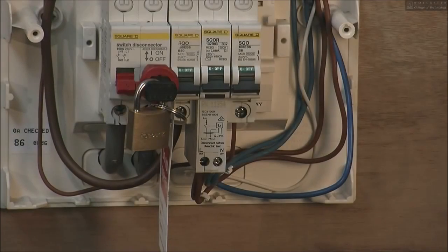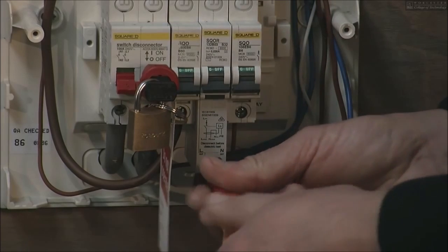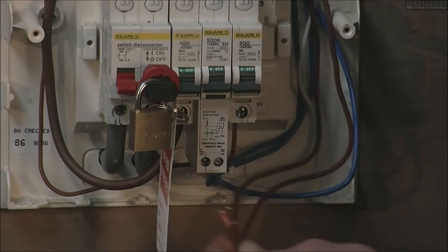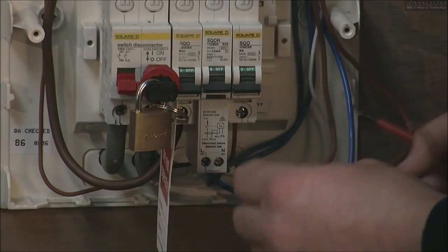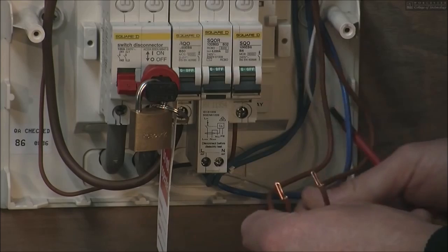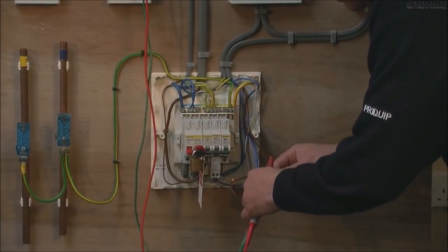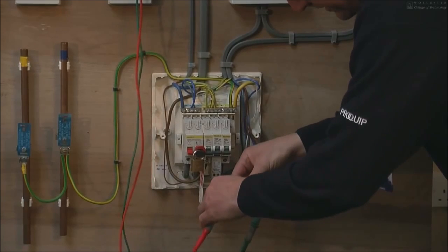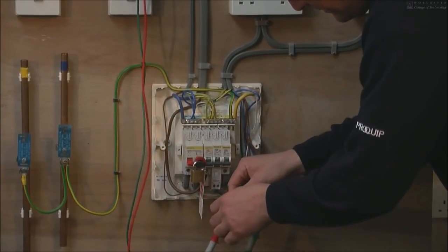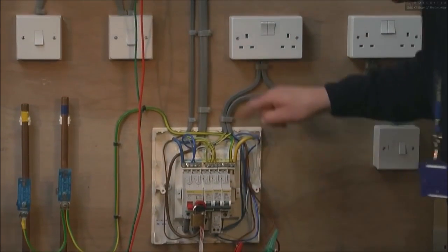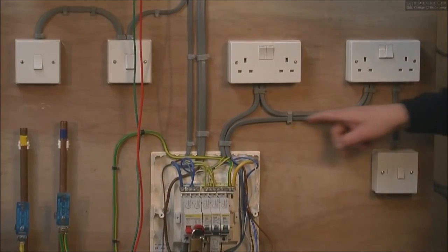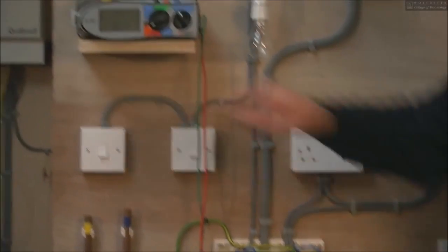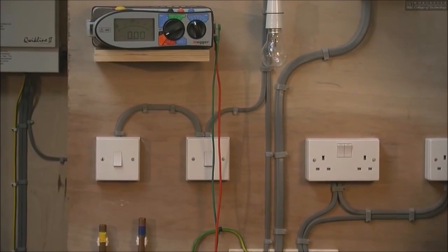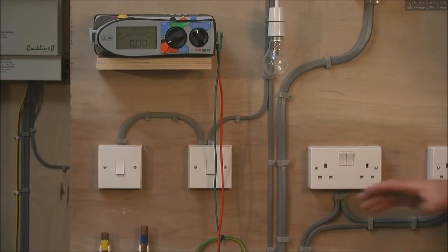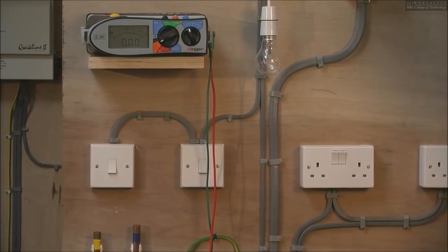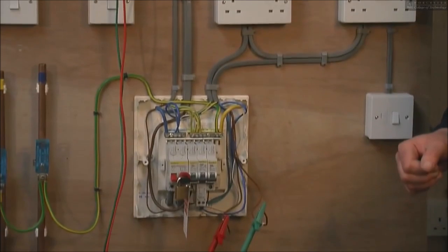This is the ring continuity test. We're now going to disconnect the two line conductors, take them out and split them. We then place our test leads onto the ends of the line conductors. This is now ensuring that the line conductors make a loop through the circuits and it's not broken. As you can see, we are reading 0.00 again. It's because the circuits are very, very small. In a house, you would probably get a lot higher readings. This is also known as the little r1 measurement.